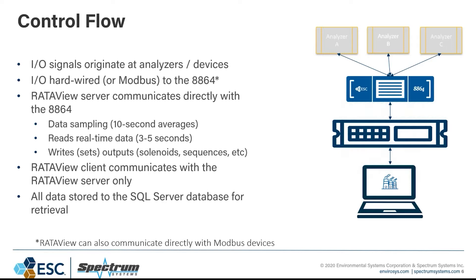The 8864 takes those signals in, and the RataView server — typically a rack mount server next to the 8864 — runs RataView services in the background, constantly communicating with the 8864. It does three main methods of communication: data sampling, where it takes 10-second averages from the 8864 and stores those in the database permanently; reading real-time data every three to five seconds for the user interface so you can see numbers changing more rapidly; and handling any writes down to the device.